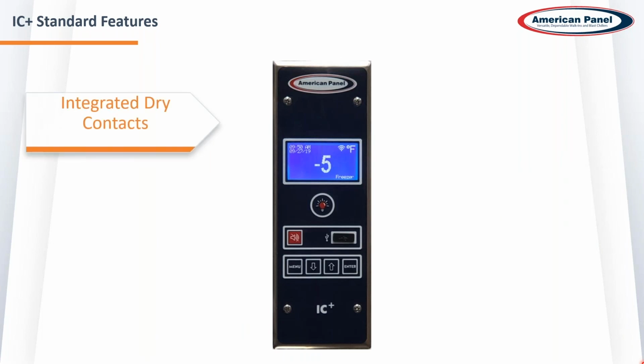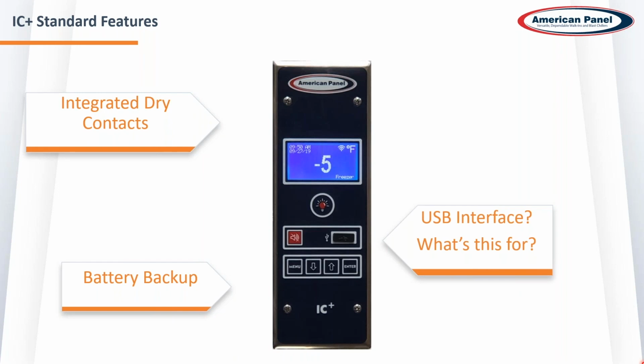Integrated dry contacts for interface with a building alarm system or building management system. This will send an output signal going out to let the external system know if there is an alarm condition on that box. Battery backup for power outages or failures. The battery will continue to send out those messages after the fact if the external systems are also so equipped with batteries. It'll also keep track of your information in there as the power goes down.